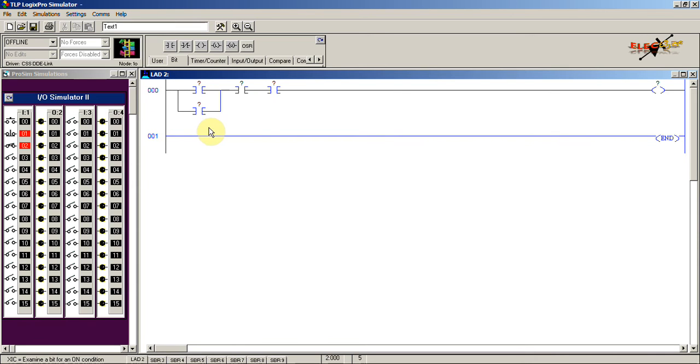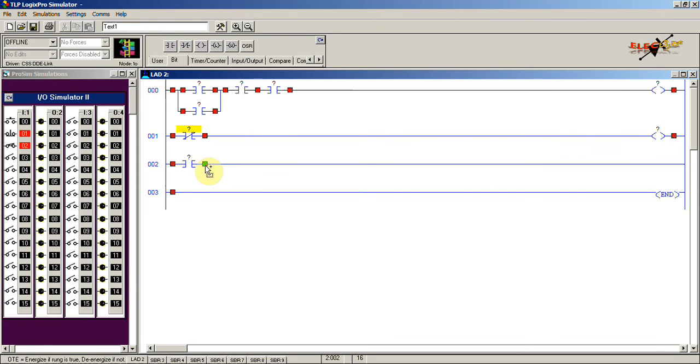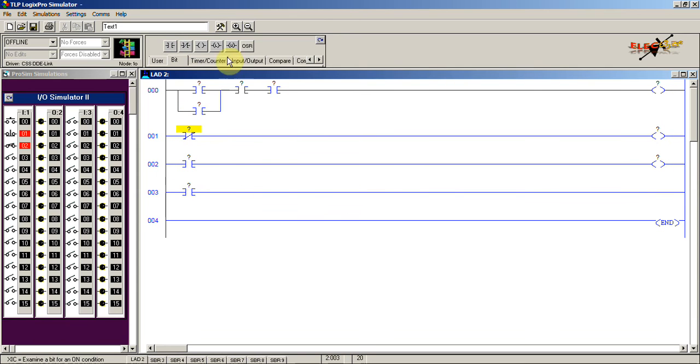The next rung we're going to use to indicate the pilot lamps, where we will indicate that motor is stopped. For that one we are going to use examine if open. So we will address later how we are going to use the address for this. And then an output, which is represented in this way here, output energize for the red pilot lamp. And in the next rung we are going to use an examine if closed instruction and one output to energize the pilot lamp which is green color, and one more instruction that we require to energize the motor starter coil.